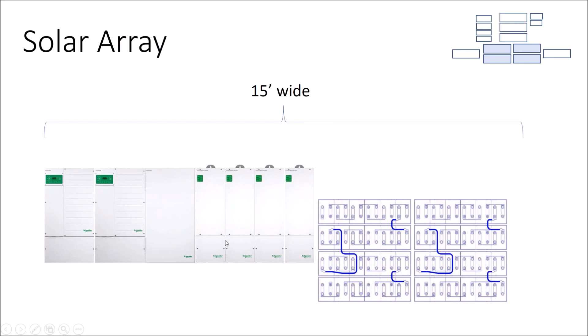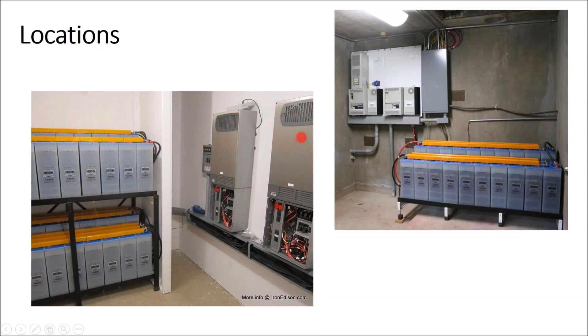Your batteries should be considered a damp location. What we see here is actually a code violation because the batteries stick out 2 feet from the wall while the panel only has 6 inches. This array is code compliant because it has the minimum serviceability depth of working space between the two. We also see these little caps on top of the batteries to capture the gas and vent it to the outside.